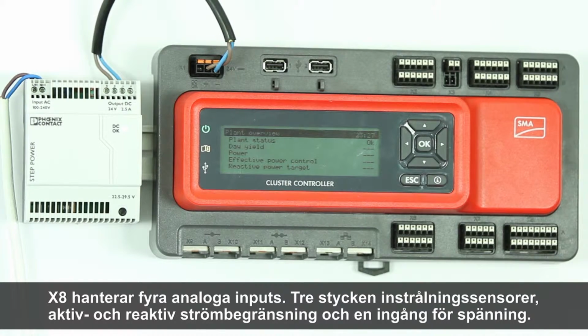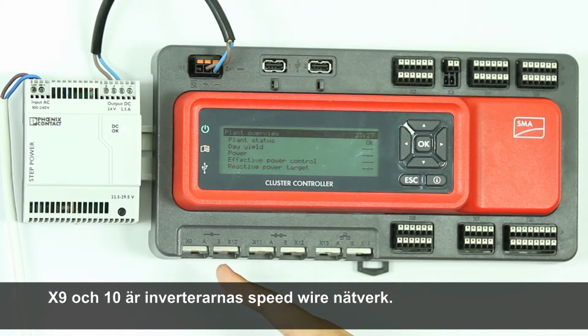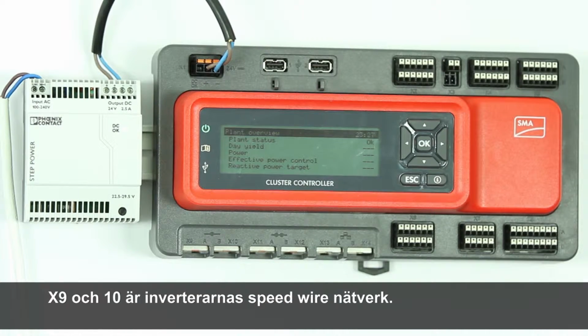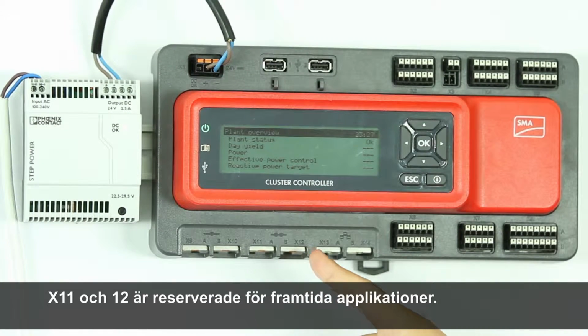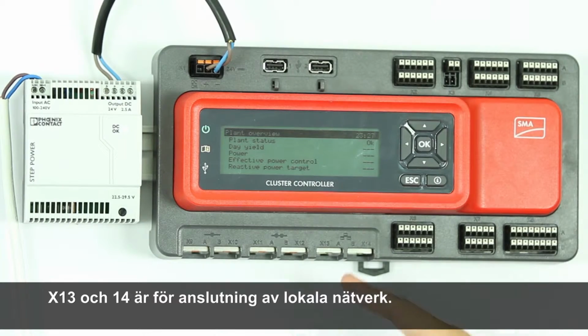X8 allows for 4 analog inputs, 3 current inputs for the radiation sensor, active and reactive power limitations, and 1 voltage input for connection of a sensor. X9 and 10 is for the SpeedWire network of the inverters. X11 and 12 is reserved for future applications. X13 and 14 are for the local area network connections.